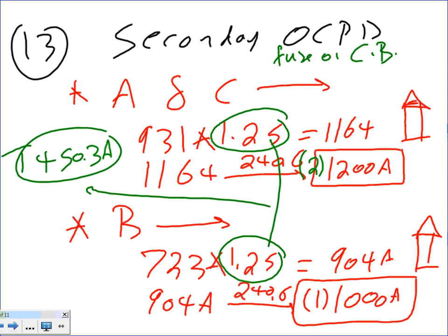Now, Camille, my friend, you look at this. One fuse is 1200 amp, the other fuse is 1000. That's okay. Now, here's what's not okay. How are you going to make this a circuit breaker? That defeats the purpose of saying it's a circuit breaker. So you almost have to go with fuses, because then you have a 600 disconnect fuse, and you put 1200 amp in this and 1000 in this, A, B. So 1200, 1200, 1000. It's the only way you can do it.